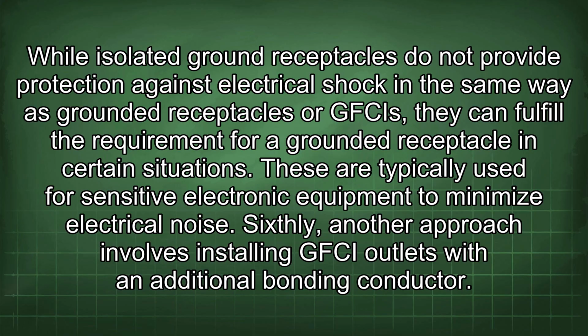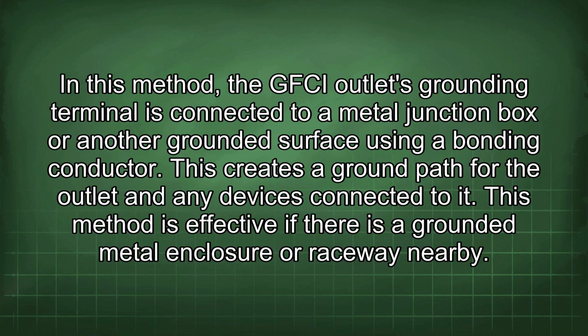Sixthly, another approach involves installing GFCI outlets with an additional bonding conductor. In this method, the GFCI outlet's grounding terminal is connected to a metal junction box or another grounded surface using a bonding conductor. This creates a ground path for the outlet and any devices connected to it. This method is effective if there is a grounded metal enclosure or raceway nearby.